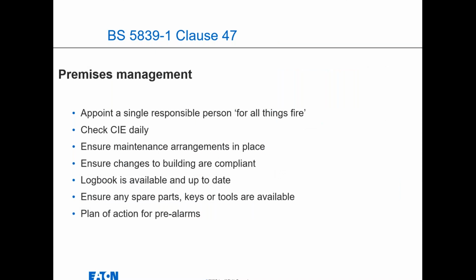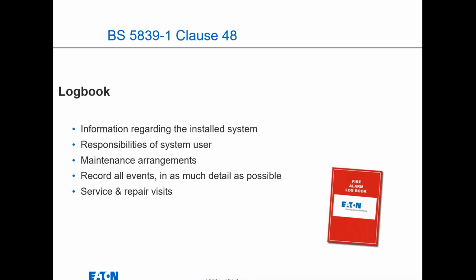So within the premises, there should be a single person responsible for all things fire, and they check the indication equipment daily. They ensure the maintenance arrangements are in place. They ensure that any changes are compliant, logbooks are up to date, spare parts and keys are all available, and there's a plan of action for any pre-alarms. And that should all be within the logbook. And again, a good place to keep that logbook is with your certification, and make sure everything's intact in that. So if there was for any reason an issue, it can all be documented.